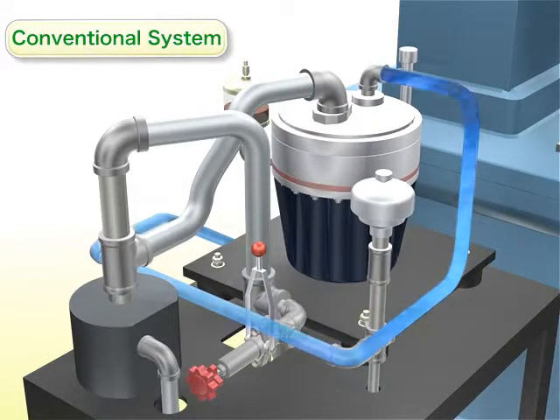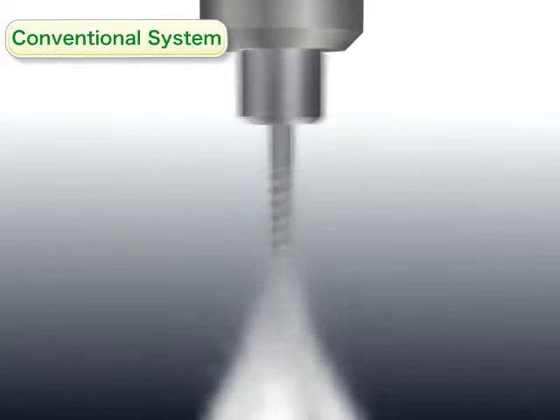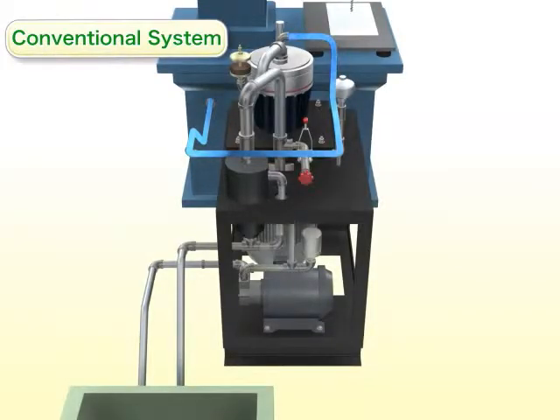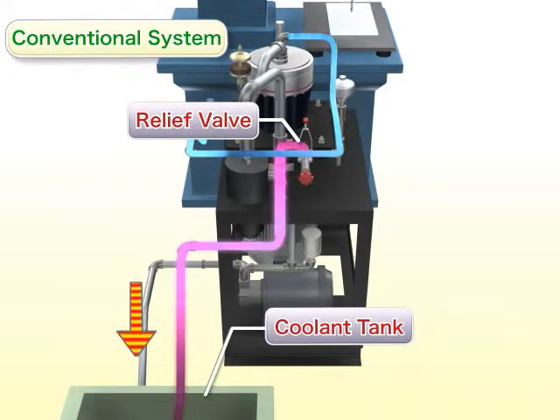With conventional systems, the high-pressure pump spins at constant speed, making its discharge rate constant. Thus, when the coolant flow rate required by the machine tool is lower than the current discharge rate, surplus coolant fluid is generated and returned into the tank via the relief valve. This is not an efficient way to use the coolant.